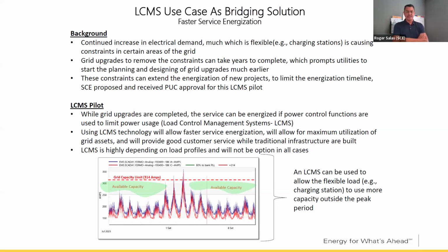So again, we have this LCMS, load control management pilot. It's a little bit different than what Alex described on PG&E. Essentially, the customer agrees to install a power control system at their site to limit power usage based on a pre-approved schedule that we determined during the engineering phase. Each project is different. The limit is based on the load profile—sometimes the most limiting component is the distribution circuit, sometimes the substation, and in some cases a higher level voltage. Nevertheless, that's essentially it: the customer installs a piece of equipment that we review and approve, and sets control limits based on what we approve.